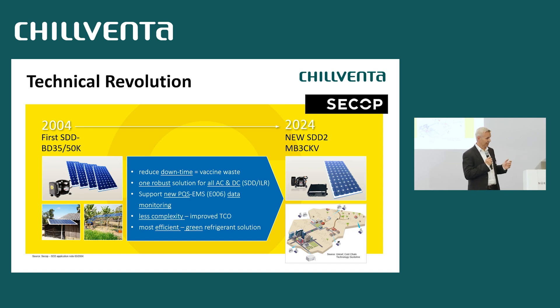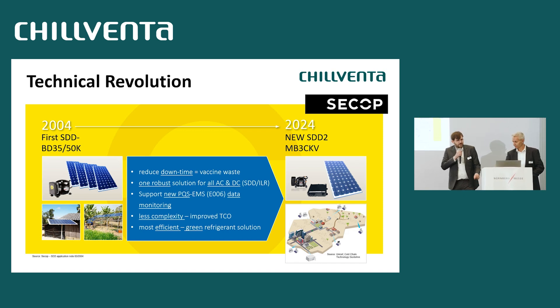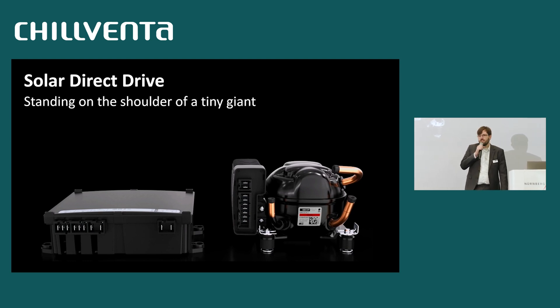The solution now: my colleague Mark Fischer will present step-by-step all the features implemented in this compressor, compressor inverter, and the full power management solution. What we had in mind when asked to provide a compressor for solar direct drive was the BD-Nano with R600A — a compressor with 100 watts in the size of a fist — with an added power supply that runs AC all across the globe from any power source, and runs on PV from any solar supply provided.